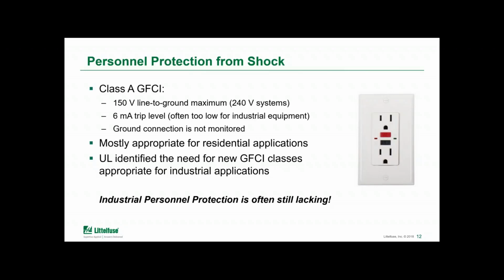And so in the residential or low power world, we have what we call Class A ground fault circuit interrupters, or GFCIs, as I'm sure you're familiar with, since the 1970s. And they really have done a good job of reducing the number of people killed at home by electricity. But then when we talk about factories and industrial facilities, often the voltages and leakage currents that are in existence in the equipment there mean that a Class A GFCI is just not going to be a viable option in most cases. So, as shown on the slide here, a Class A device is intended for systems at 150 volts, line to ground or below.